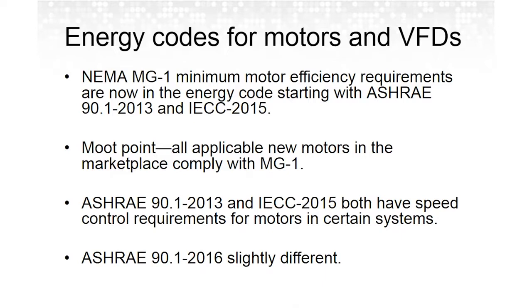Okay, and I am moving too slow, so I will try to speed up a bit. With all the code and standard background stuff, you're probably asking yourself, when are we going to discuss VFDs specifically? Well, here's the lead into it. Minimum efficiency requirements for motors are dictated by NEMA MG1, which again is incorporated into 90.1 and IECC, the two applicable energy conservation codes. And it's sort of moot because, again, this is a federal standard.